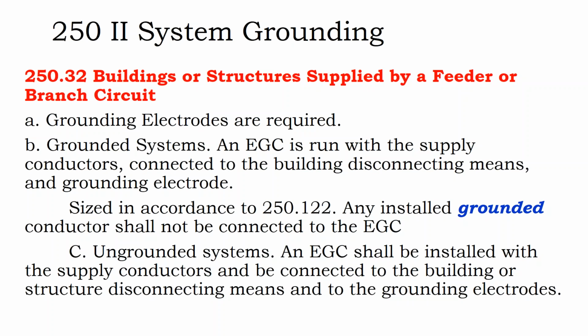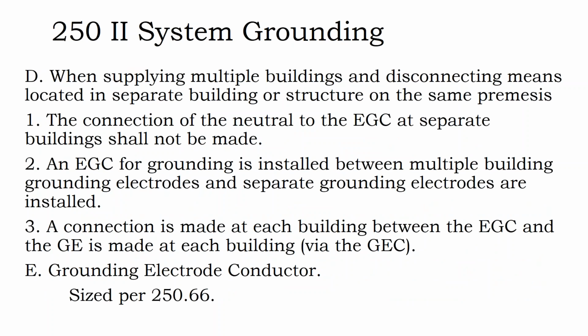Now we get into our sizing tables, and we see for ungrounded systems, an equipment grounded conductor shall be installed with the supply conductors and connected to the building or to grounding electrodes. So even if your inverter is an ungrounded inverter, you still have an equipment ground conductor. When supplying multiple buildings and disconnecting means located on the same premise, the connection of the neutral to the equipment ground conductor at the separate building shall not be made. So if you're designing a microgrid and running multiple buildings off the same microgrid, you still only want that one neutral to ground connection. An equipment ground conductor for grounding is installed between multiple buildings, and grounding electrodes and separate grounding electrodes are installed.